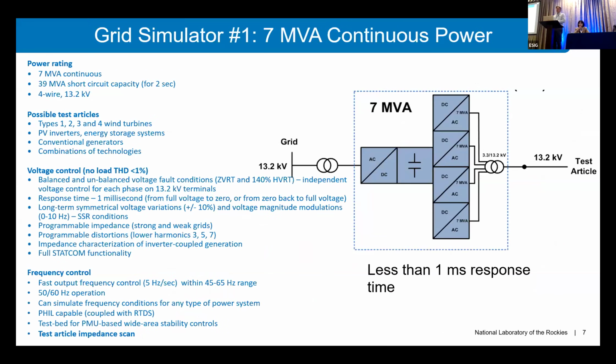Just a few notes on grid simulators, a little bit more detail. I won't go through all the specs, but our first grid simulator we commissioned back in 2013, 7 MVA. It's back-to-back AC, DC, DC, AC conversion, with outputs of 13.2 kV. It can support up to 40 MVA for short periods of time, which is good for testing doubly fed induction generators and things like that that have high fault currents. It has a 1 millisecond response time, so it's pretty quick.